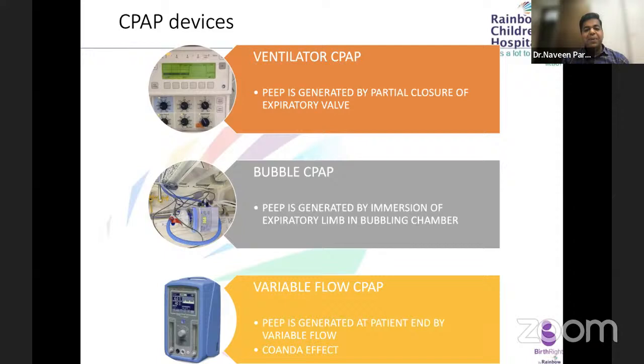So the same thing we are replicating artificially, whether that is in the ventilator CPAP, the bubble CPAP or the variable flow CPAP. In ventilator CPAP, it is the expiratory valve which closes partially. In bubble CPAP, we do the same thing by dipping the expiratory limb in a water chamber. The extent to which it is dipped in the water chamber becomes our pressure. So that pressure is generated, and then the baby has to expire against that pressure. And in that effort, the work of breathing is good, because the alveoli don't collapse. So in bubble CPAP, PEEP is generated by immersion of the expiratory limb in the bubbling chamber.